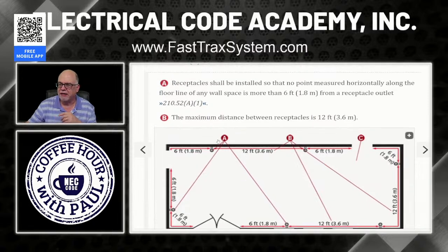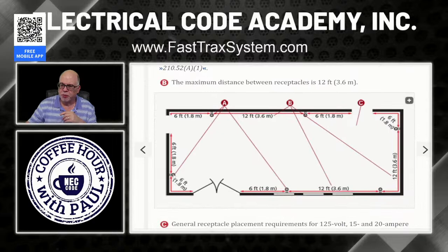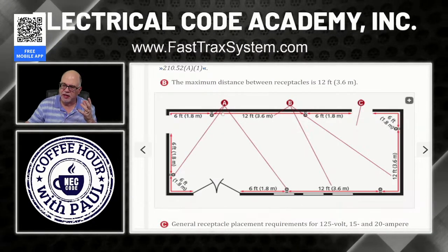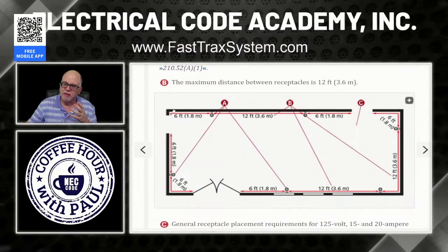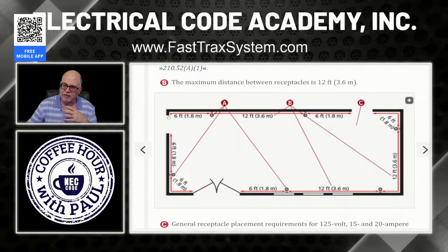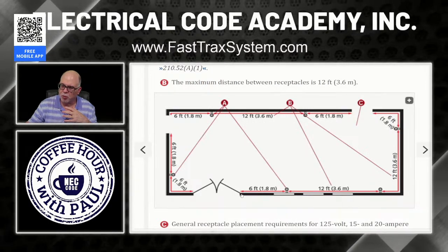So let's talk about it right here. A is pointing right here, and here, and here. What is the commonality between all of these that it's calling out? They're all within 6 feet of a break in the wall line. This receptacle is within 6 feet of this break in the doorway. This receptacle is within 6 feet of this break. It's within 6 feet of this break. And this one right here is within 6 feet of this break in the door. Right here, break in the wall.